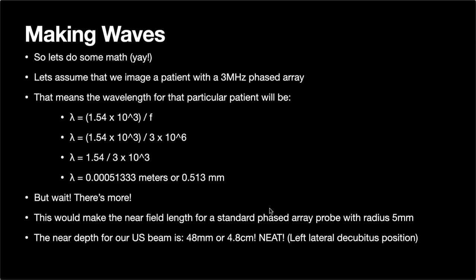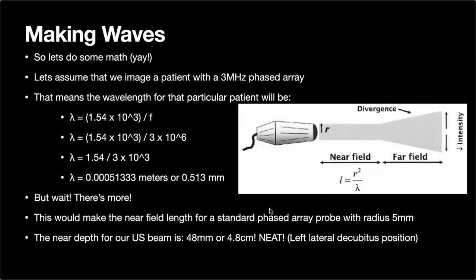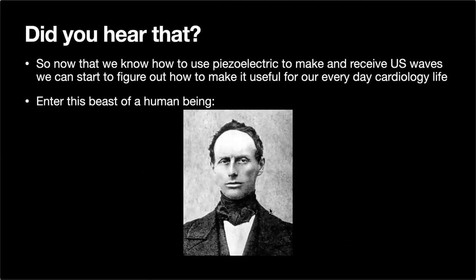Plugging in the near field equation at three megahertz, the near field is actually 4.8 centimeters. For cardiology residents: when the echocardiography technologist says to have patients roll onto their side or bring the heart to the chest wall, it's because you can utilize the near field advantages of the ultrasound probe. Getting the heart closer means the near field encompasses more of the heart structure, giving you much better image quality.